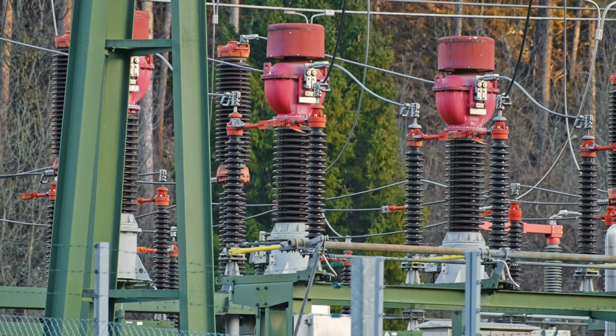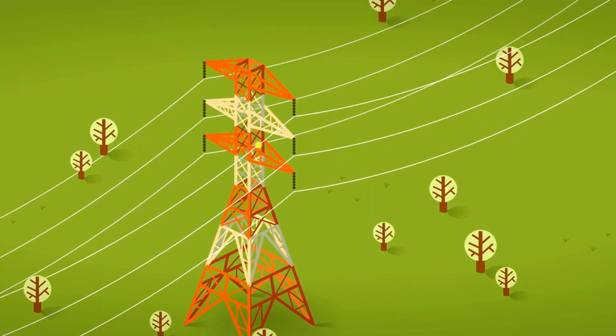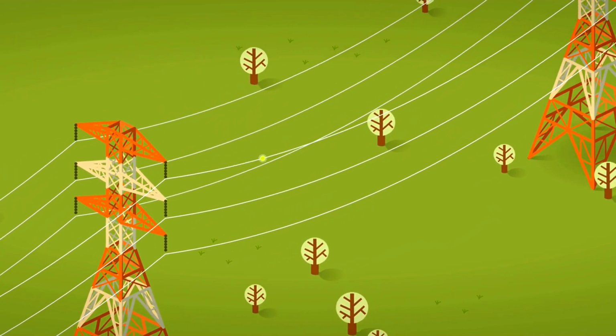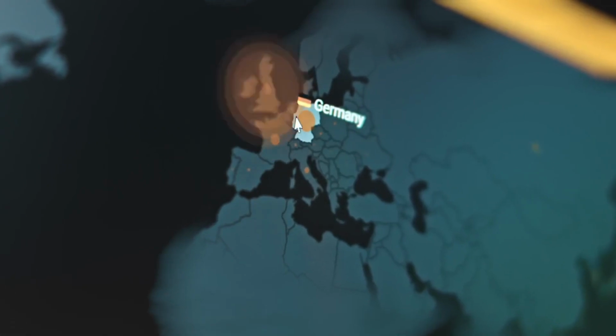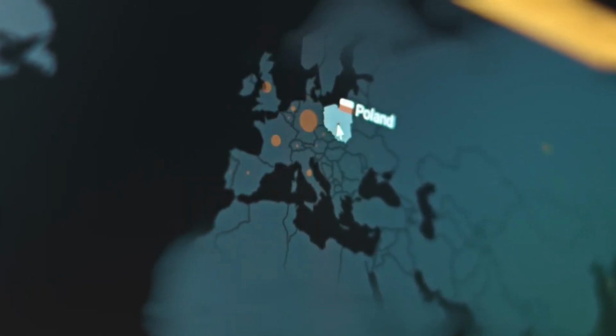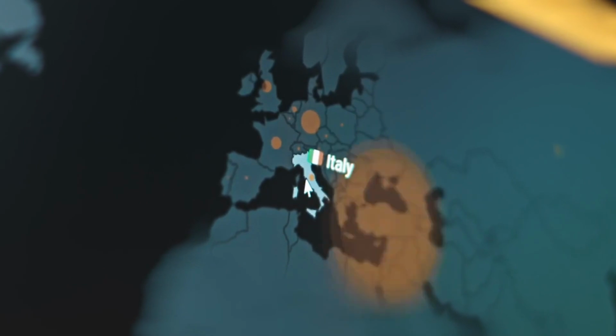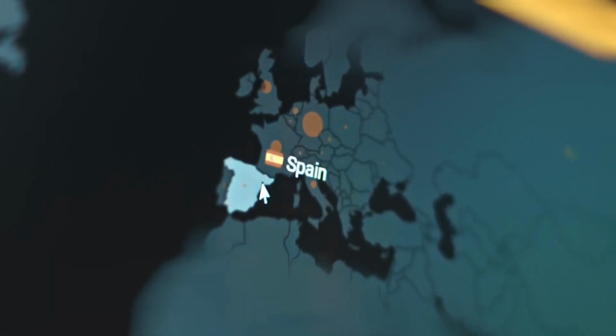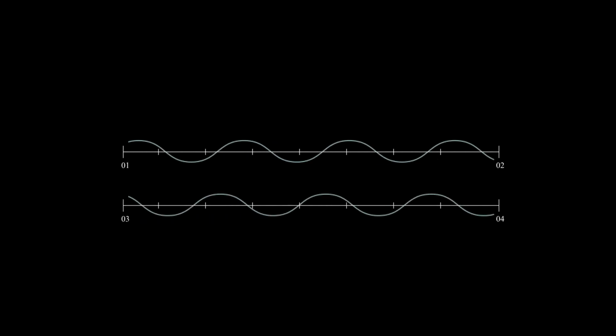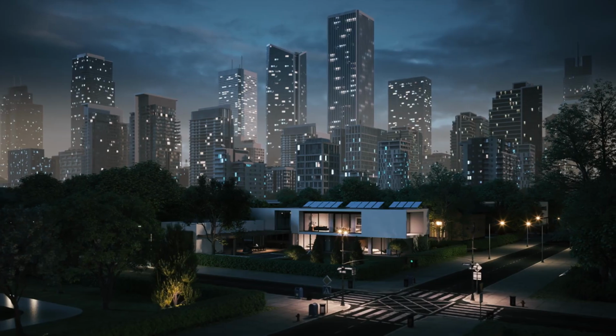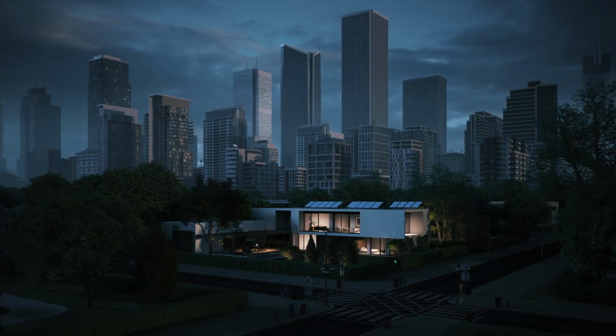What makes this case even more complex is what happened before the blackout. Approximately 30 minutes prior to the incident, two unusual oscillations were detected between the Iberian grid and the rest of continental Europe. These power and frequency swings, subtle but significant, hinted at instability building quietly in the system.